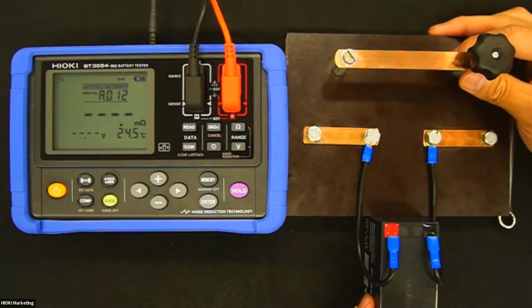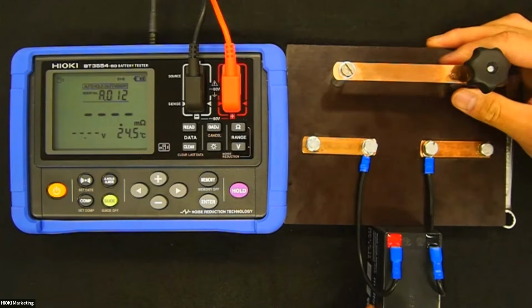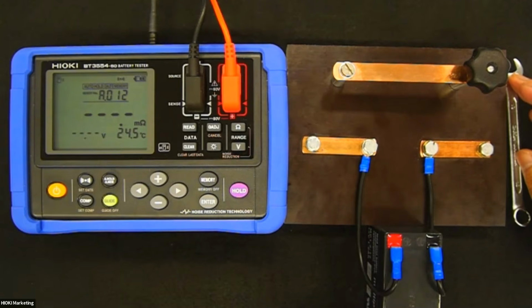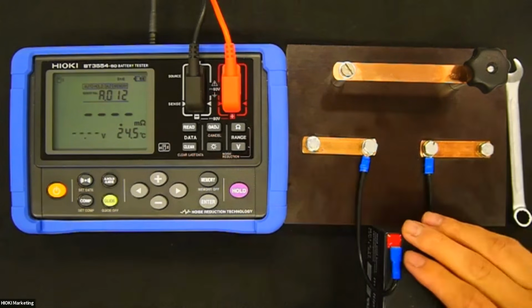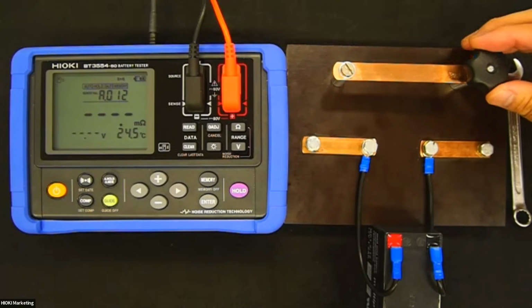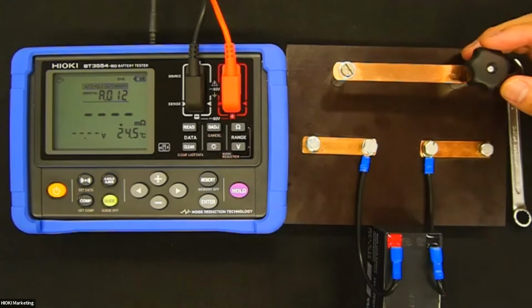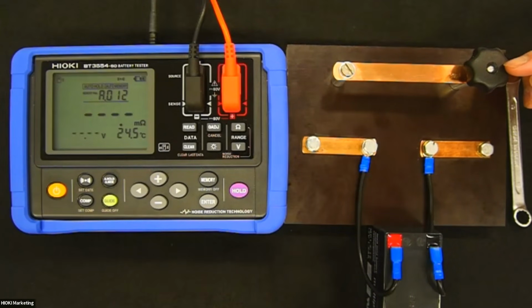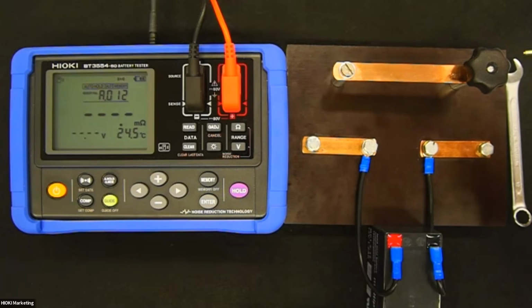One point about judgment: when making a threshold for the judgment, usually the UPS uses a plastic-covered board for safety reasons, which normally has holes on top to contact the probes for maintenance purposes. But this plastic-covered board has a slightly larger connection resistance compared to other types of boards.